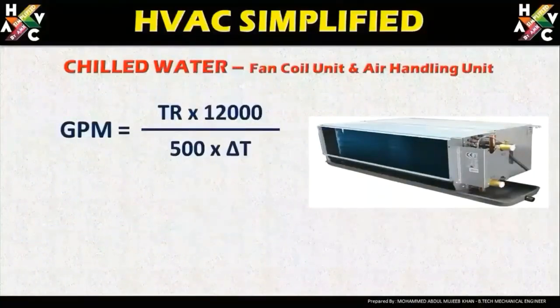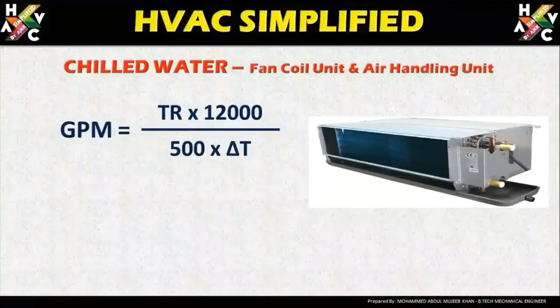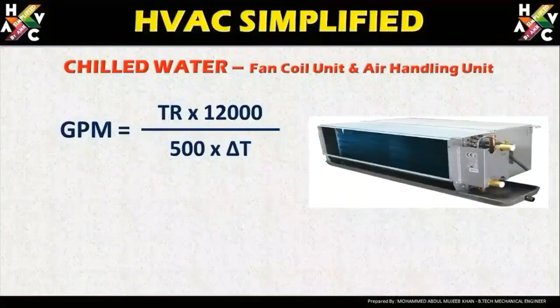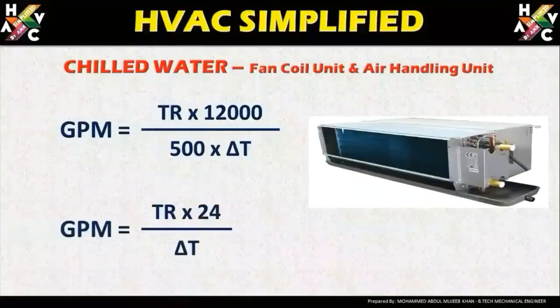The formula for GPM is: GPM = TR × 12,000 divided by 500 × ΔT. This can also be simplified as GPM = TR × 24 divided by ΔT.